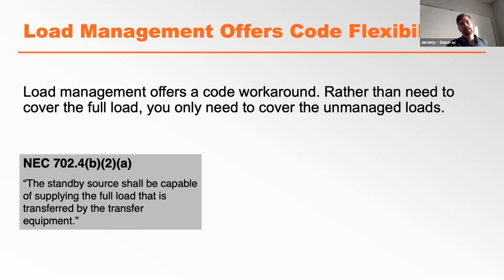It's also worth noting that load management can provide a clean solution to compliance problems. If your AHJ, for instance, enforces NEC 702, it has to do with how much backup power you need to make available for the given loads in a given scenario. If your AHJ has been enforcing 702, you may have had to be very strict with how you sized your subpanel, or you may have been forced to sell more storage than you really wanted to. Maybe you even lost jobs because of this.